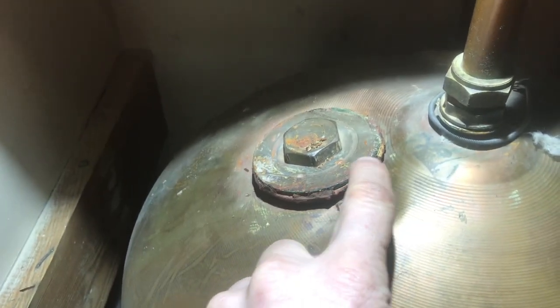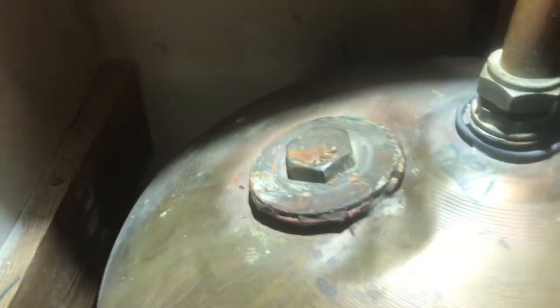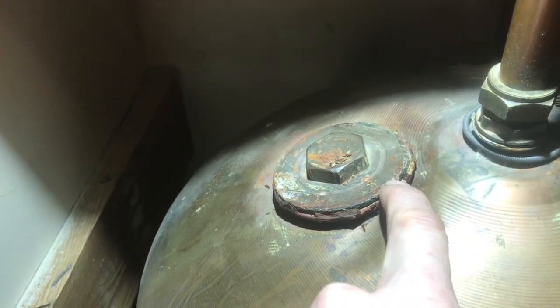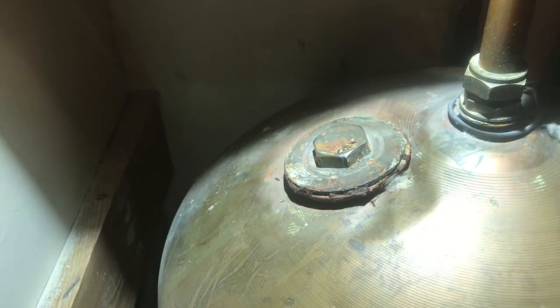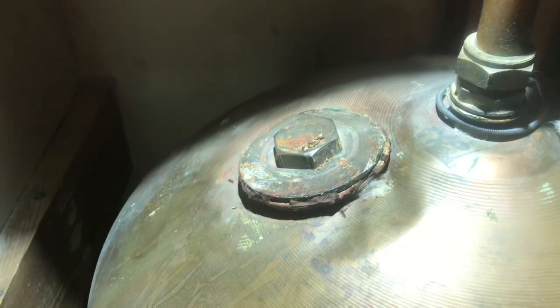This is the cap we need to remove — you can see it's got a few hammer and chisel marks around the outside. We tried to undo it but it was completely seized up, so with a hammer and cold chisel we've been knocking it with little shocks. Amazingly, after about 50 or 60 taps it suddenly turned, and now we can simply get the big wrenches on and undo it to gain access.